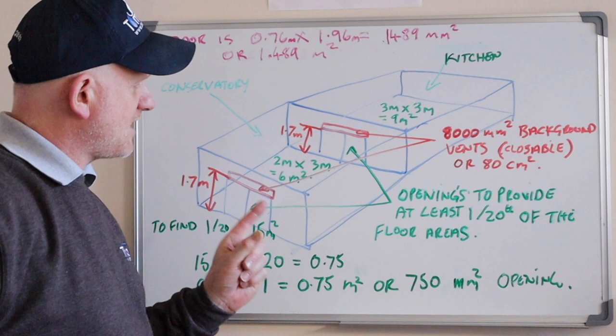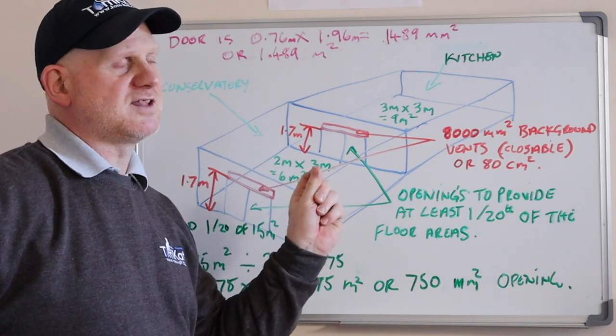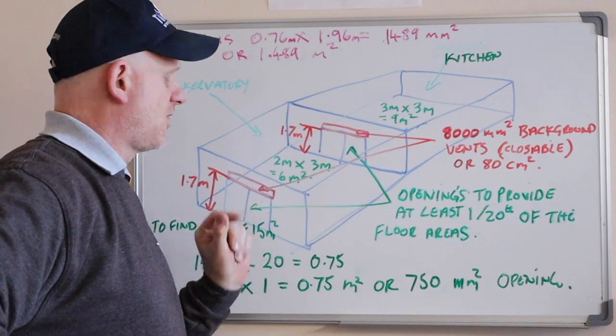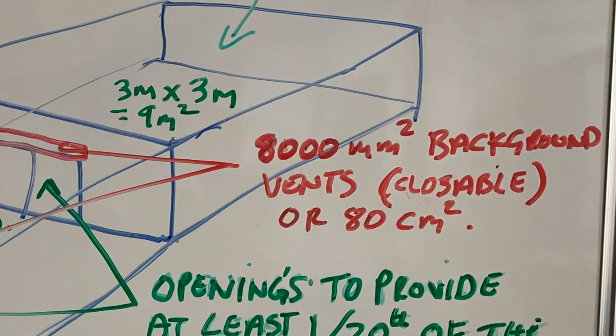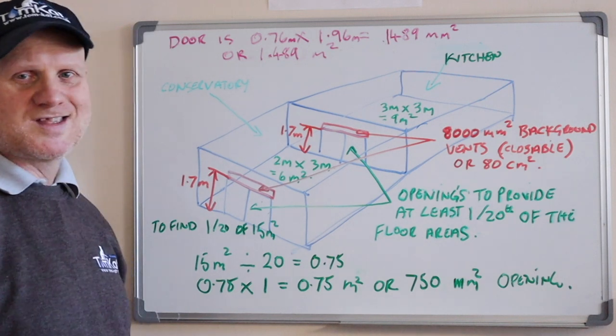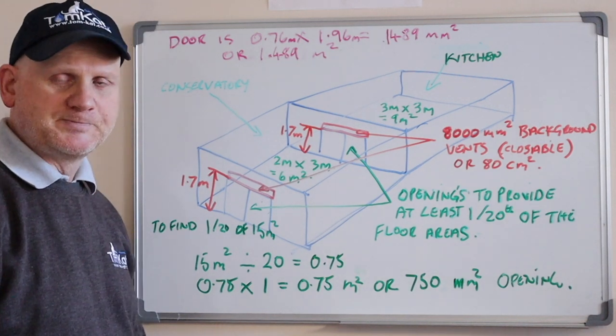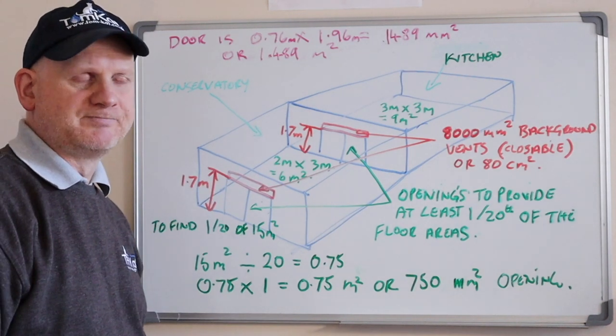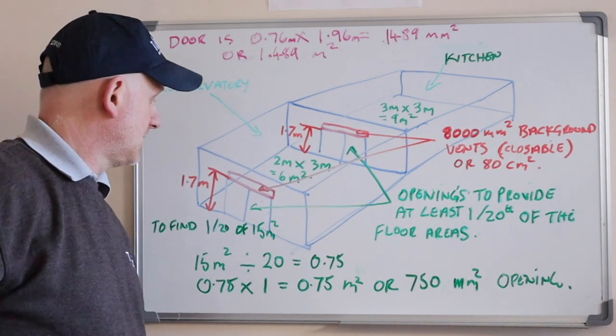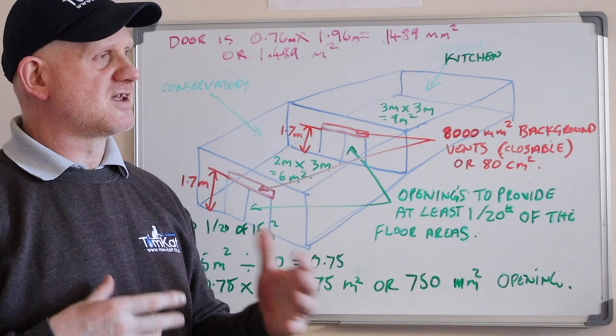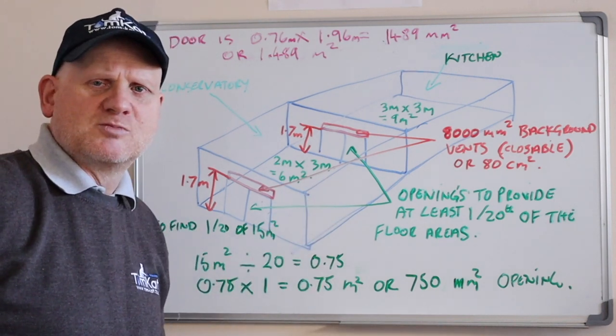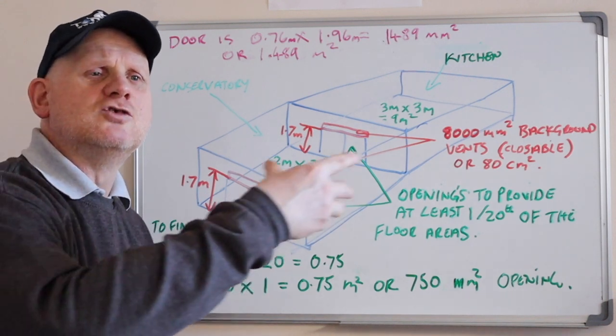We also need to provide background ventilation of 8,000 millimetres squared — that's 80 centimetres squared — going from the kitchen through to outside. That vent needs to be closeable and positioned more than 1.7 metres off the floor. Importantly, normal gas vents for a gas appliance cannot have fly screens and cannot be closeable, whereas this building regulations vent must be closeable because it's ventilating the room, not the gas appliance.